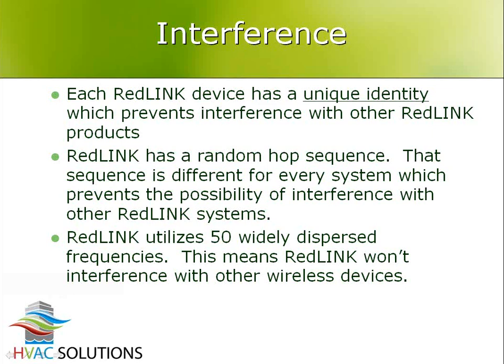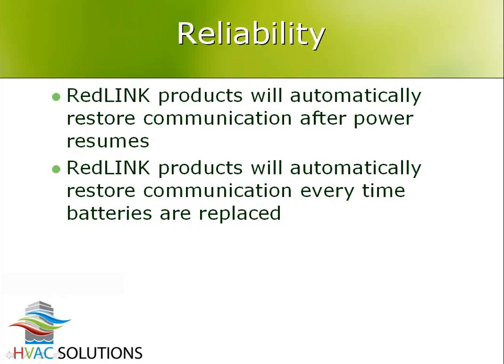And there is, like I said, a random hop sequence, so if there is a possible interference, it will jump to another frequency. And you have up to 50 different frequencies, so the chances of you conflicting with your neighbor are pretty slim, unless you have 50 Honeywell stats, and then maybe there's a problem. We'll find a way to solve that. If you have a power failure, whether it's because there's a power failure in the home or whether it's a battery version of one of these stats and the batteries fail, in either case, when you resume power, they remember their identities, they remember who they're supposed to communicate to, and they resume communication immediately after having power restored.